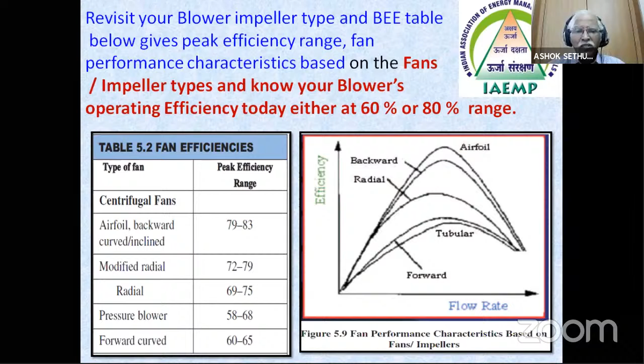The fan affinity laws, we apply to all the centrifugal fans, and to some extent to axial flow fans also. They may not follow exactly one-to-one, but it is applicable to all the centrifugal variable torque loads like fans and pumps. Whatever the flow is across the fan, for a 10% increase in the RPM of the motor or the fan, there is a 10% increase in the flow. Whereas a 10% reduction in RPM on this fan, automatically the static pressure, or the back pressure, reduces by almost 20%. And when you reduce the RPM by 10%, the power to the fan reduces by 27%.